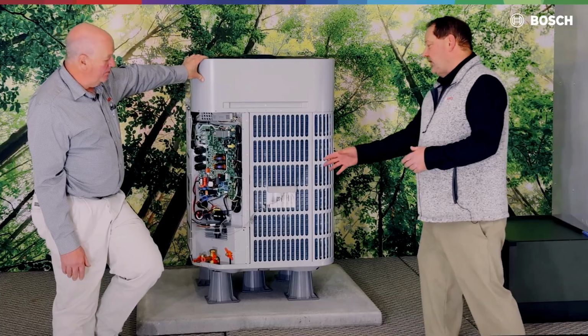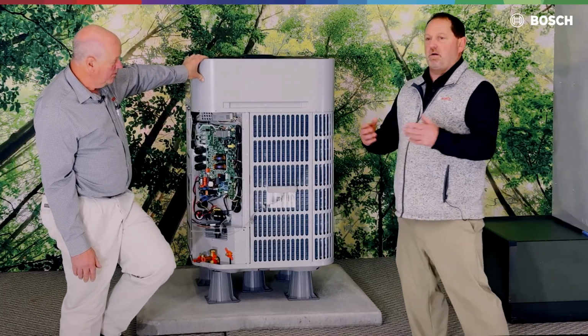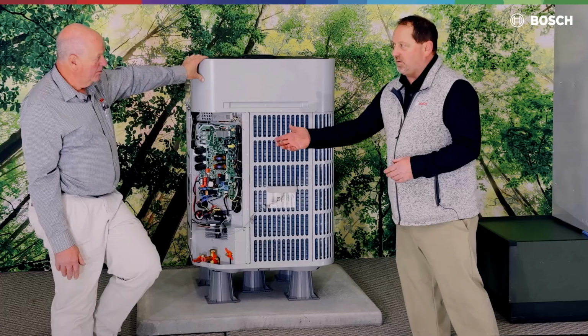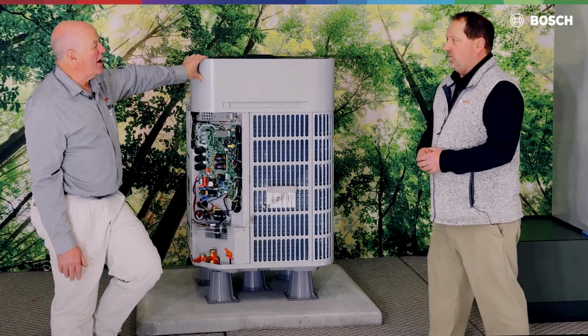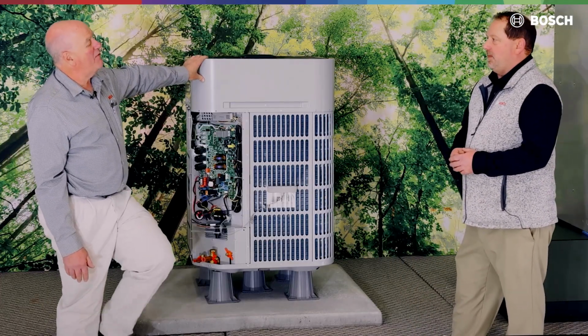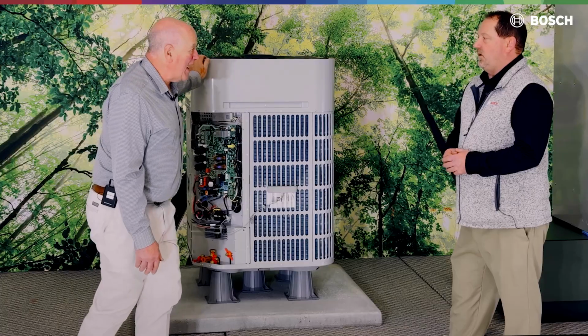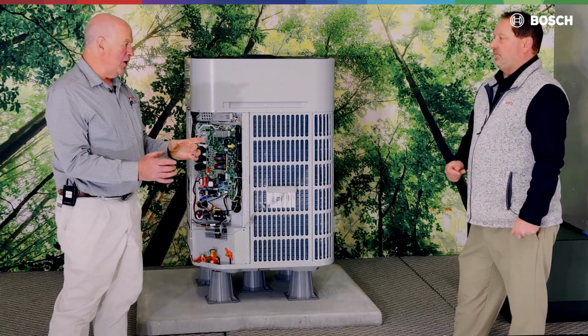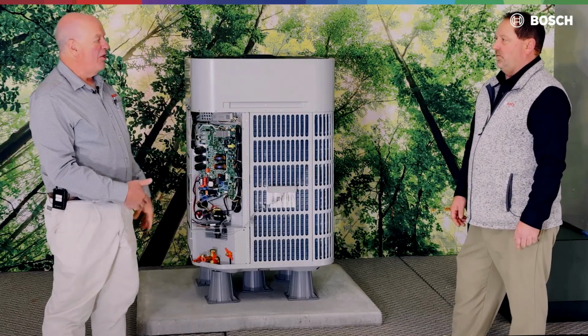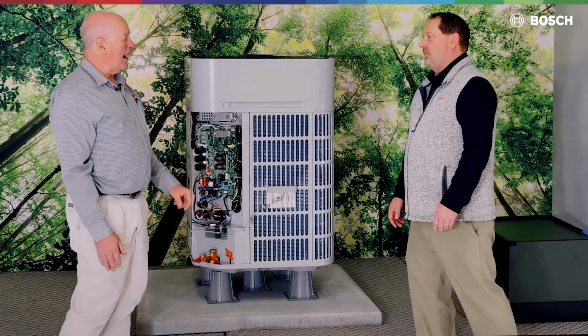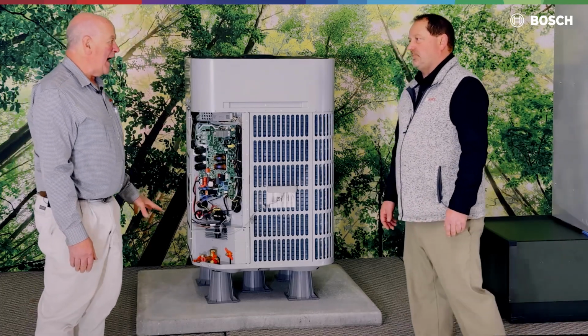But on a line set and evaporator coil only, we're not in a moisture environment. Should I be able to get lower than 350? Probably you can if your vacuum pump is good, and depending on whether you're using quick evac hoses. They make a quick evac kit that has the 3/8 hoses. They pull the valve cores out. They pull down really quick if you go that route. If you're doing standard, then maybe an hour or two.